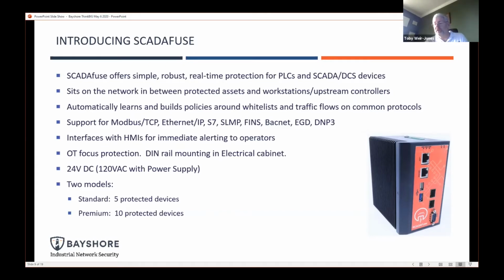It has a built-in Modbus server, so it can be integrated into your SCADA systems, whether it's iFix, whether it's CIMPLICITY, or any of these other tools. The idea there is that your control room is the first line of incident response. It's the facility you already have and the people who are already sitting there. And what they're looking at is whether or not the device has logged events, because events are situations that deviate from policy.